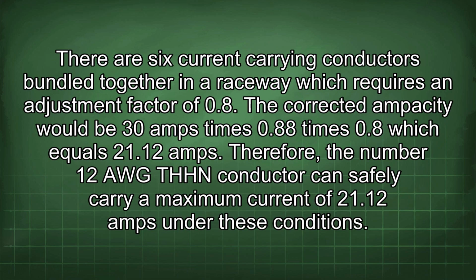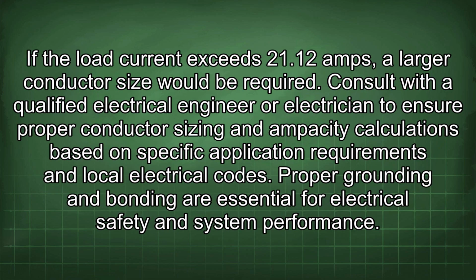There are 6 current-carrying conductors bundled together in a raceway, which requires an adjustment factor of 0.8. The corrected ampacity would be 30 amps times 0.88 times 0.8, which equals 21.12 amps. Therefore, the number 12 AWG THHN conductor can safely carry a maximum current of 21.12 amps under these conditions. If the load current exceeds 21.12 amps, a larger conductor size would be required. Consult with a qualified electrical engineer or electrician to ensure proper conductor sizing and ampacity calculations based on specific application requirements and local electrical codes.